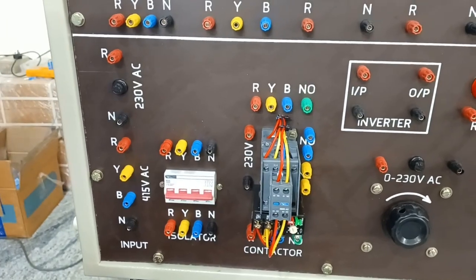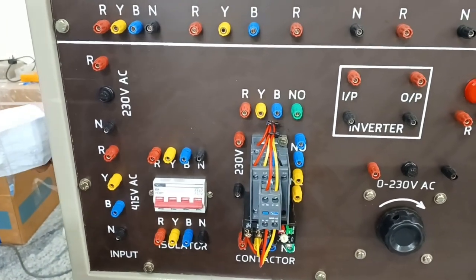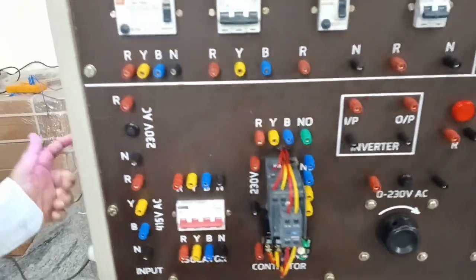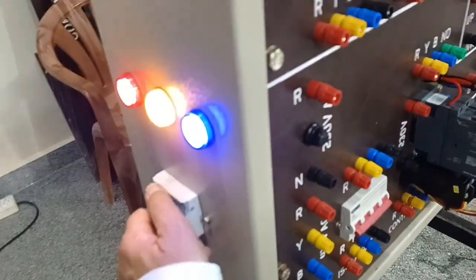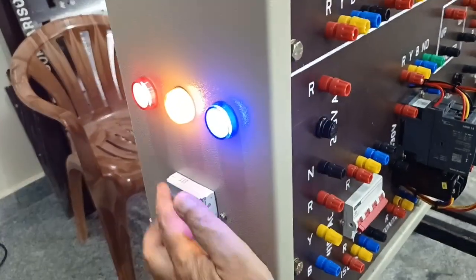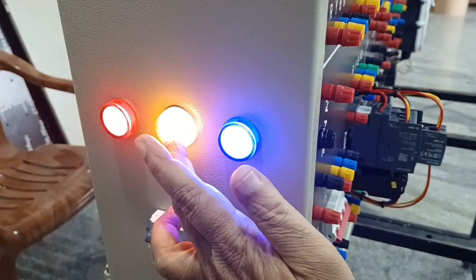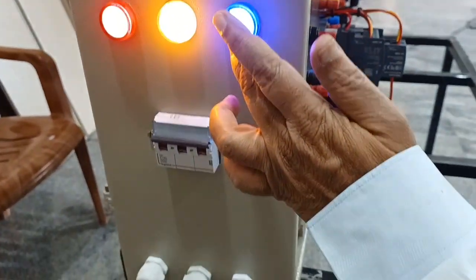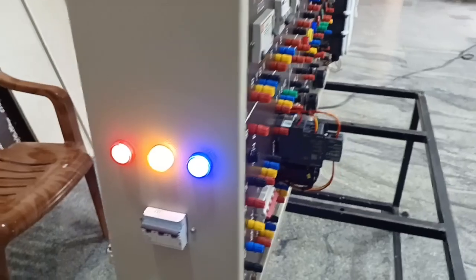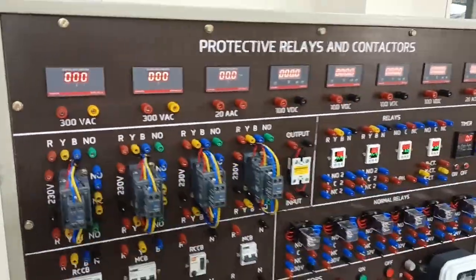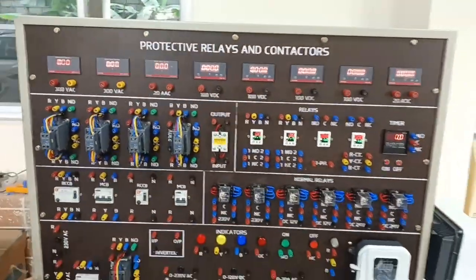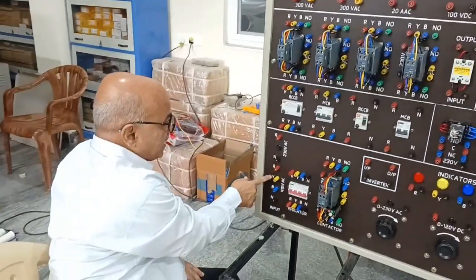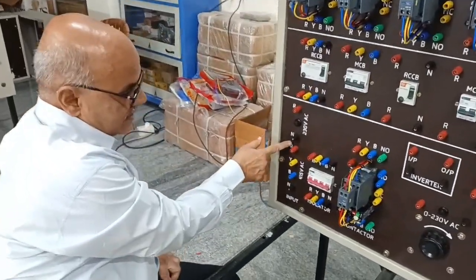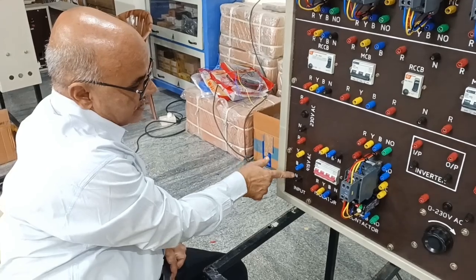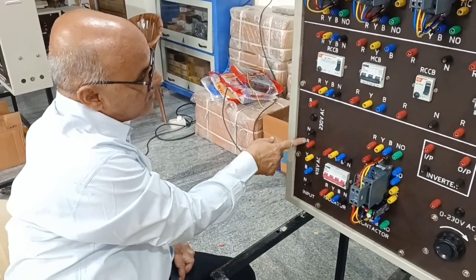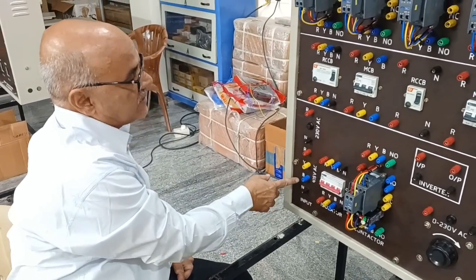And then when you switch on and apply 3 phase supply, there is a mains MCB here. Once you switch on this, your R indicator, Y indicator, blue indicator should glow. So once you switch on, all my meters will glow. Simultaneously, you will get 3 phase supply here. You will get fixed 3 phase supply R, Y, B and N. Whatever the input voltage will be, you will get the same voltage.